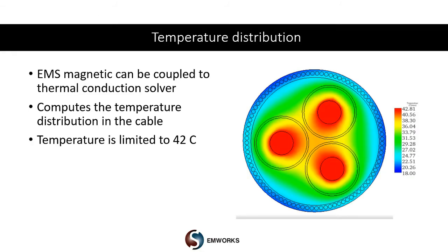Finally, let us take a look at the temperature distribution. EMS can be coupled with a thermal conduction solver. Together, the magnetic and thermal conduction solvers compute the temperature distribution in the cable as you see here. For this particular cable, the maximum temperature is limited to 42 degrees centigrade, which is within the design specifications for the cable.